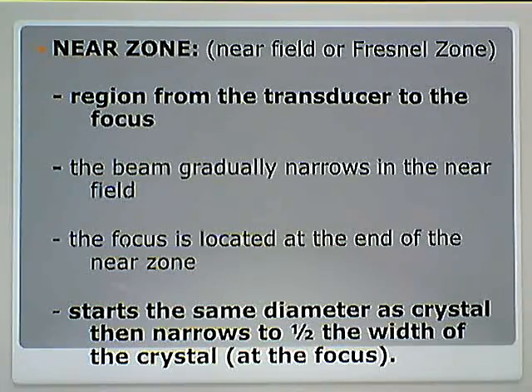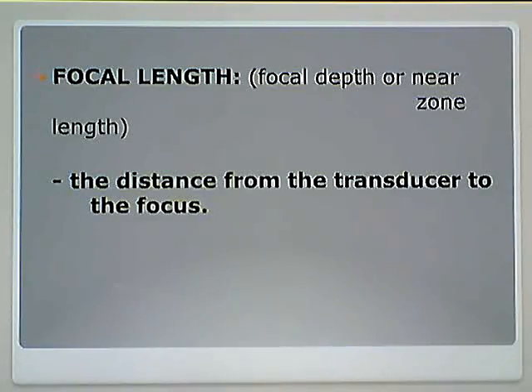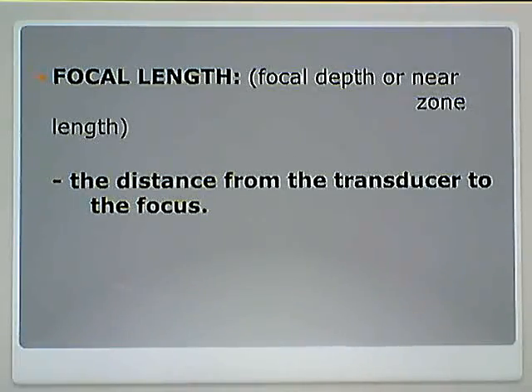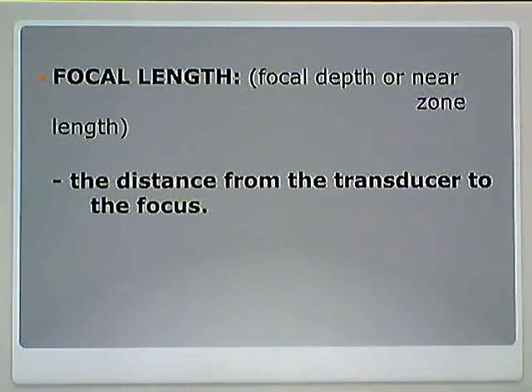The near zone starts the same diameter as the crystal, then narrows to one-half the width of the crystal at the focus. The focal length — also called the focal depth or near zone length — is a distance. It is the distance from the transducer to the focus. When asked about a distance, think length. When asked about an area, think zone.